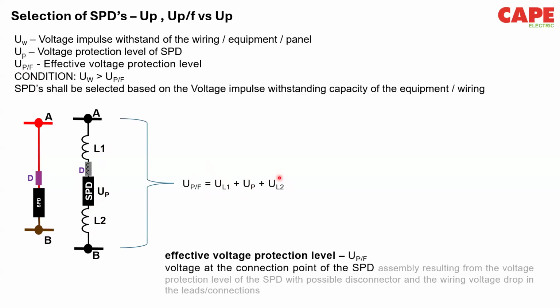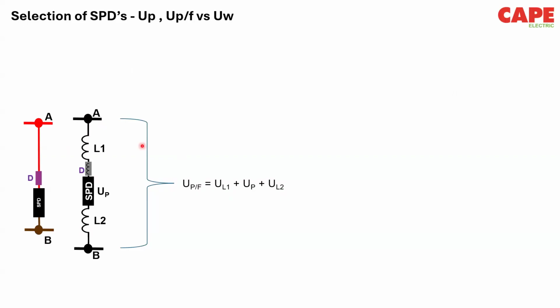Okay. So let me show you a small calculation. But before that, UW is the voltage protection or impulse withstand of your equipment. That means, for example, if it is a class 3 equipment, like a lift, it is tested for 4 kV. Okay. So your SPD UP, or this total UPF, should be less than 4 kV. And generally in standards, we say it should be 80% of that of the equipment.